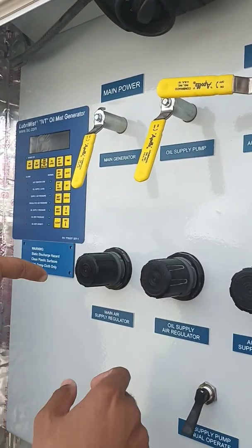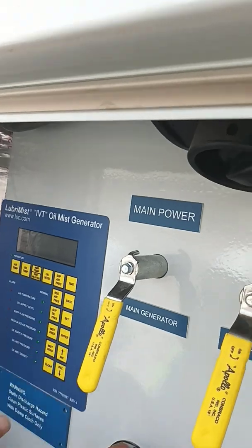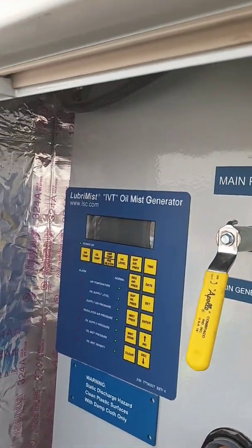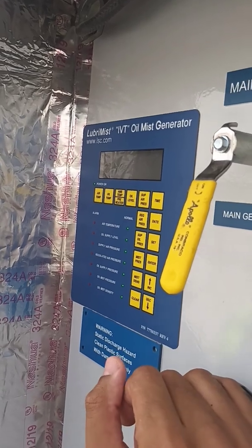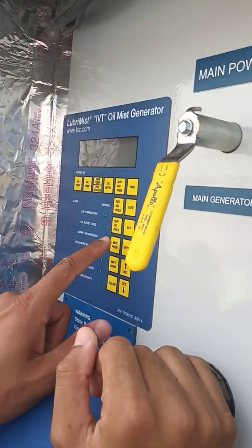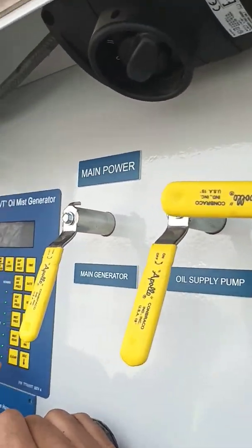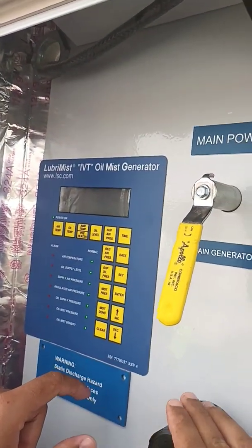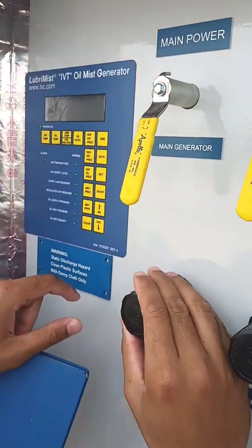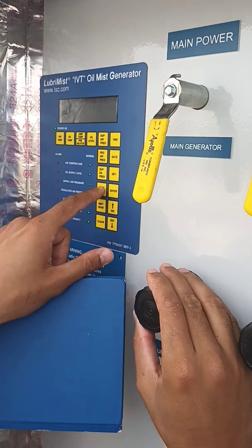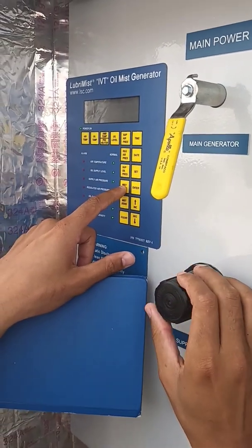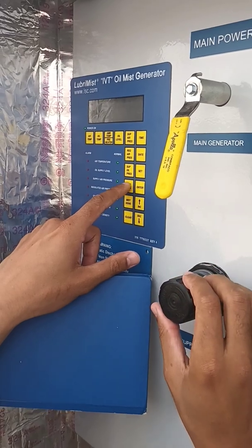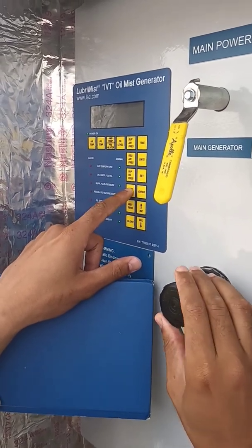So what you do now that you can adjust it, you see the mist pressure, and I want you to bring it down to 50 millibar. Clockwise you increase and anti-clockwise you decrease. So you see your regulated pressure. It should be about 1 point. I think it was 1.15. No, 1.33. We will see. Now 63 millibar. Down, 50.